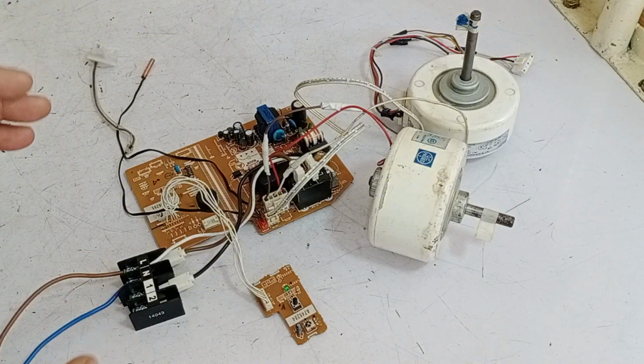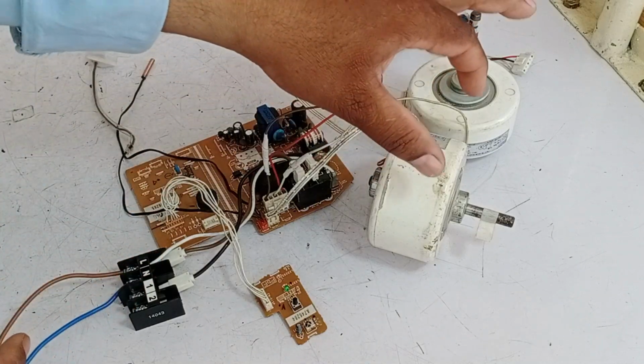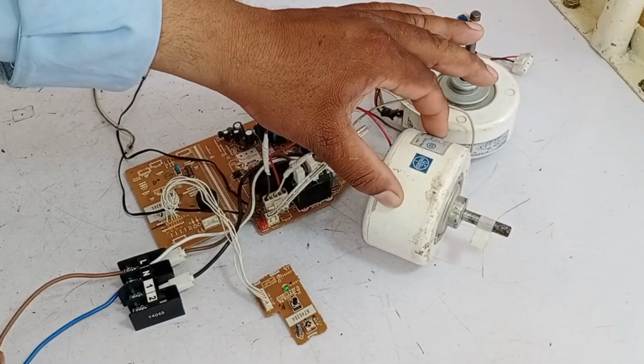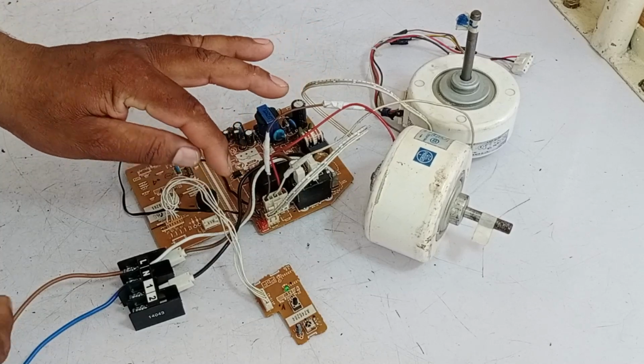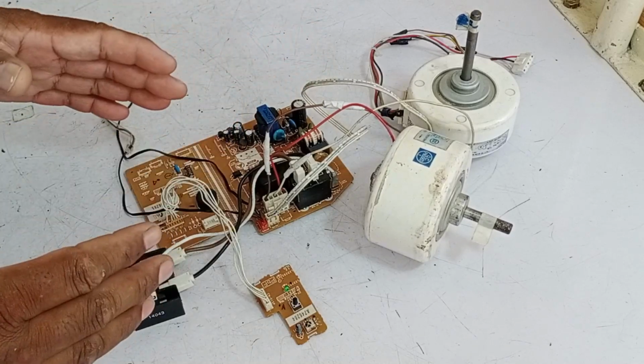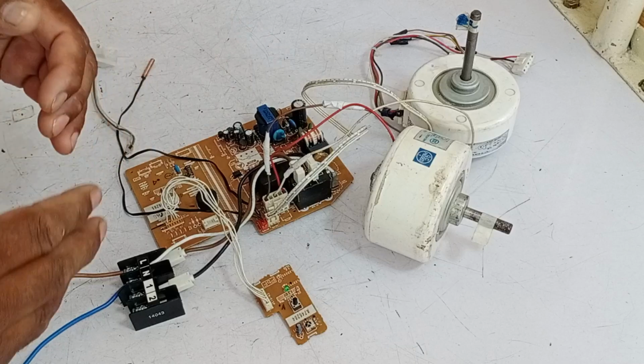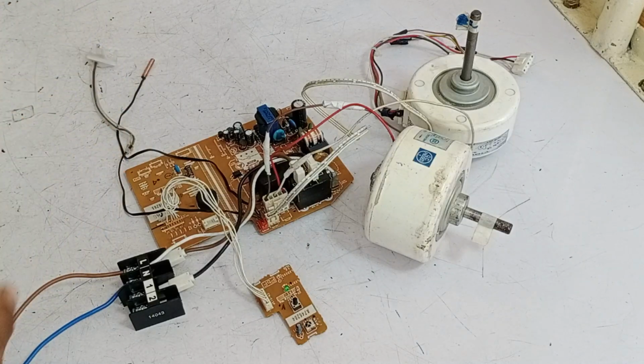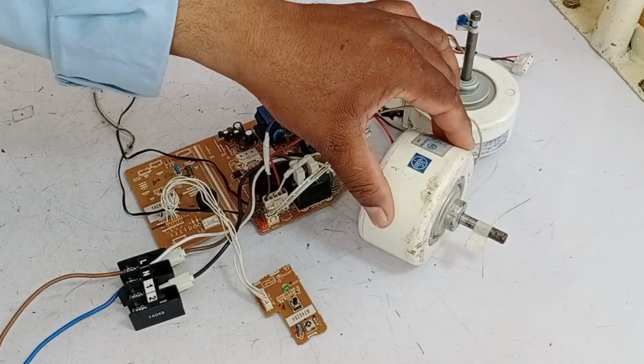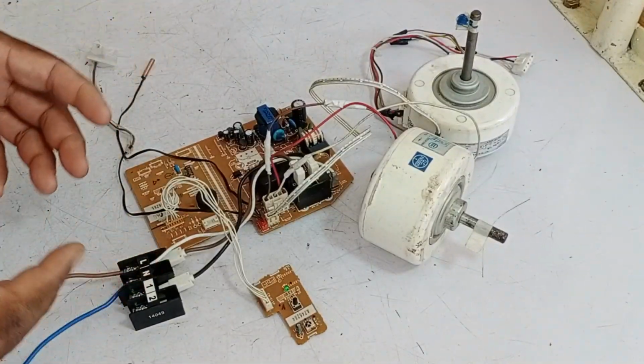If the motor starts, then stops, and the output shuts off as well, meaning the compressor trips, this indicates that the fan motor might be faulty. Its feedback is not functioning correctly, and the PCB is not receiving a proper feedback signal, causing repeated tripping. Sometimes it works, sometimes it trips. To fix this, you can try directly replacing the motor. This might resolve the problem.